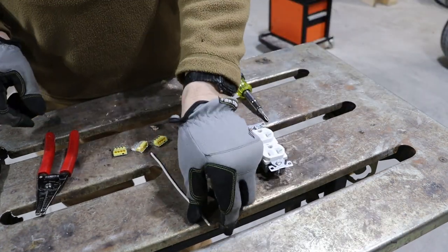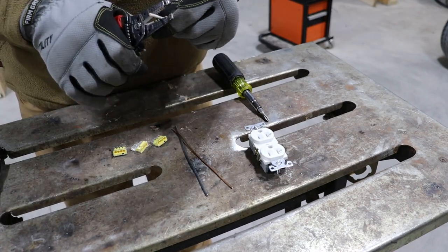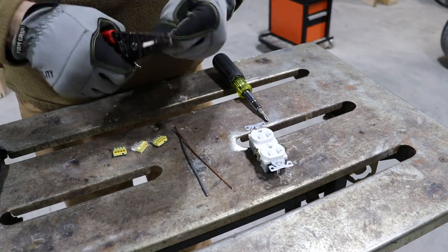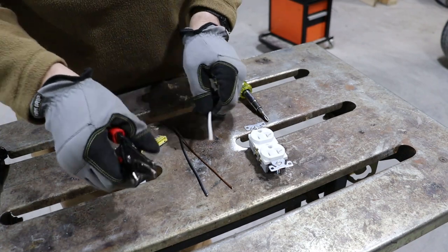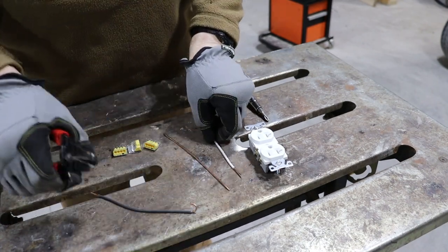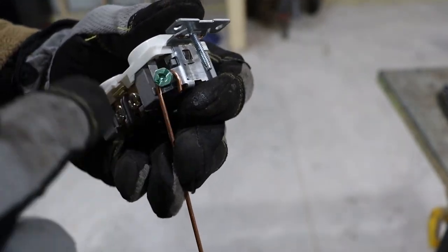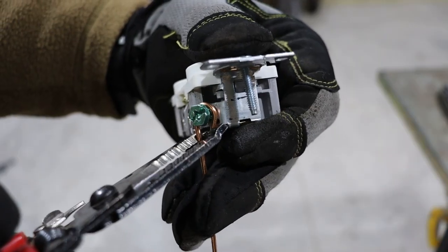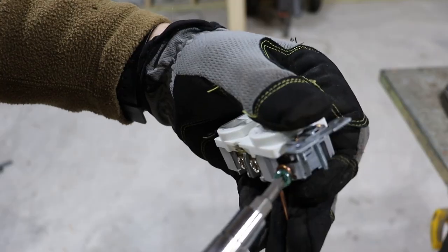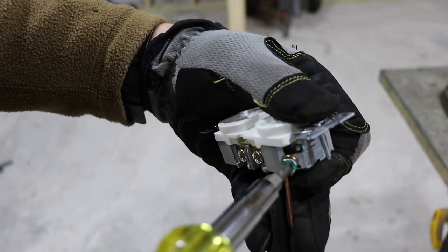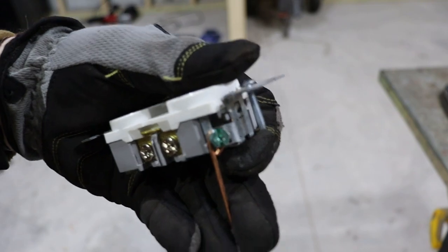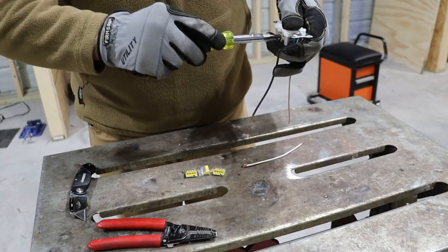Be left with three wires. Strip one of the wires off about three-eighths of an inch and the other one about three-quarters of an inch. Go ahead and make a loop on the wires. On these screws, they're all going to tighten clockwise. You want to put your wire on such that when you tighten this screw down, it's also going to tighten your wire up.